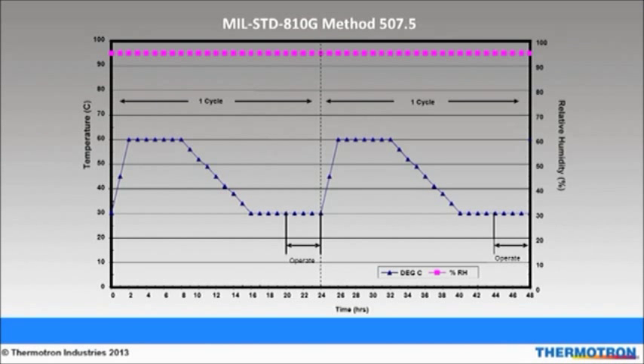This figure is from MIL-STANDARD 810G method 507.5 and the procedure is called aggravated cycle. Its purpose is to subject a product to elevated temperature and humidity conditions. The cycle begins with 95% relative humidity at 30 degrees Celsius and then heats up to 60 degrees Celsius. The temperature stays at 60 degrees Celsius for six hours. Next, we cool down to 30 degrees Celsius and soak at that temperature for four hours. After that, we turn the product on and allow it to soak at the same temperature for another four hours. We maintain 95% relative humidity throughout the entire cycle. After this first cycle is complete, taking 24 hours total, it is ready to be repeated.